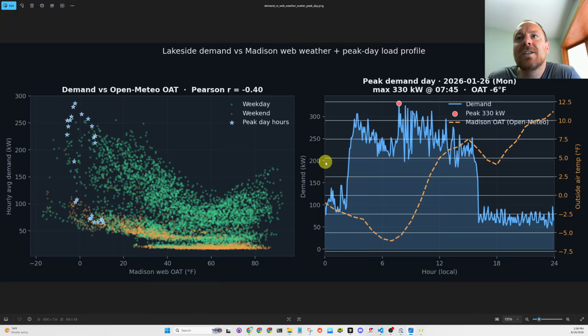So the idea is that in theory, if you ran the building 24/7 and maintained it at temperature during these cold snaps that usually last at least 3 days in Wisconsin, or any cold place in the world, 3-4 days, it's very common for people to run the HVAC system 24/7 during cold heating or cooling events. Peak July, humidity is really high, and you could probably do something similar.